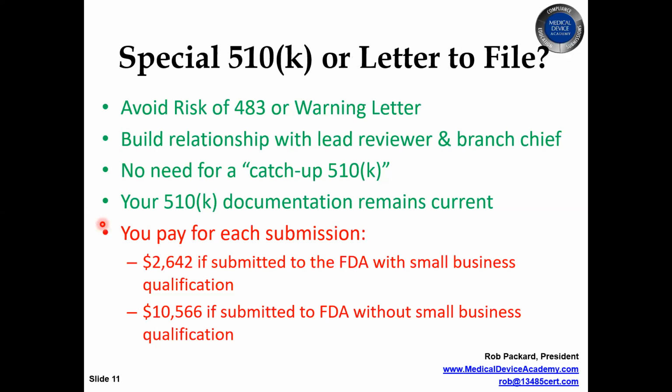And so you want to avoid that scenario, particularly if you're a foreign company, because if you get 2 warning letters, then you're put on import detention and can't ship anything into the US until it's resolved. Another reason is you don't want to have a catch-up 510K. If you continually, every time you make minor modifications, you submit a special 510K, then you're not going to have to do a catch-up 510K later on.